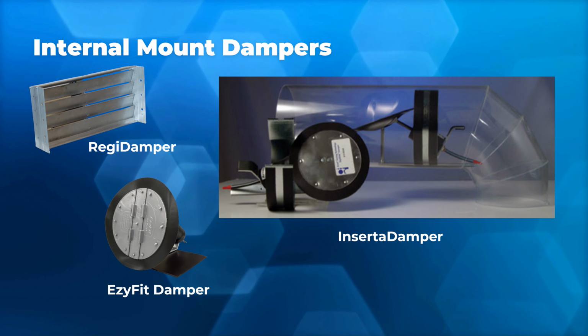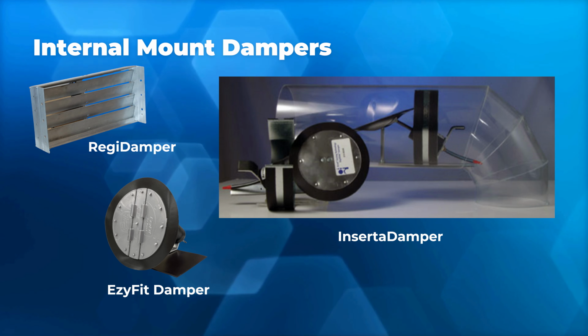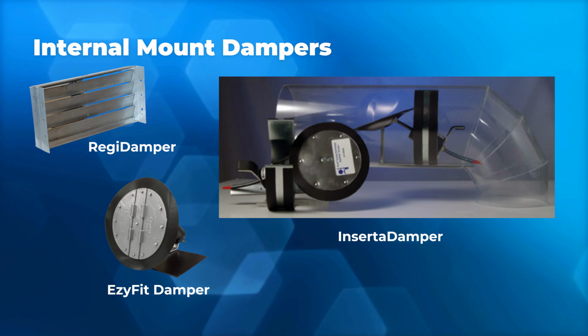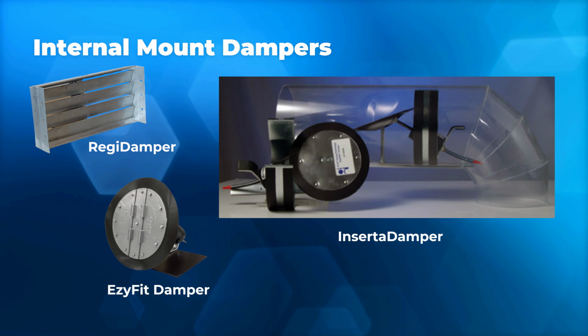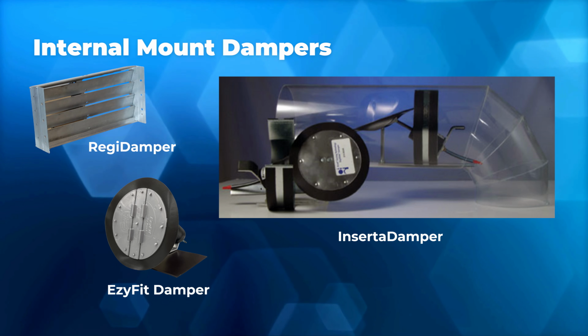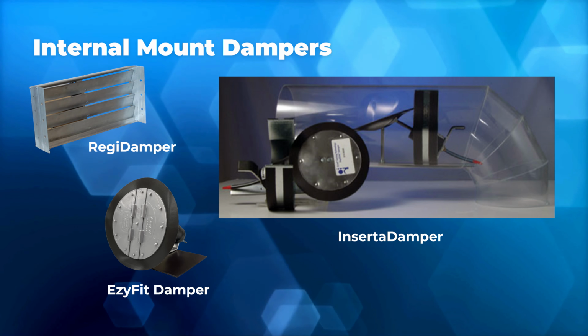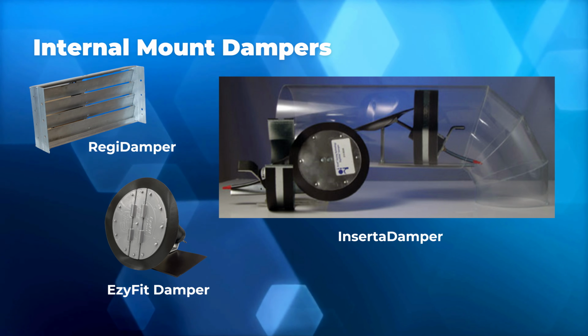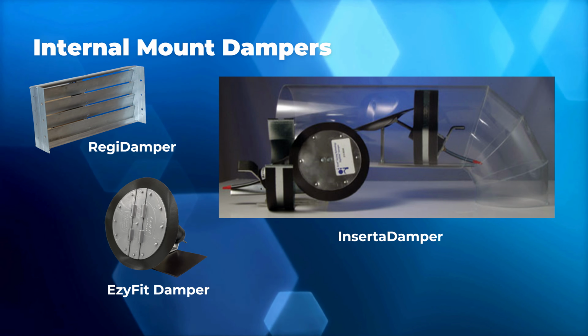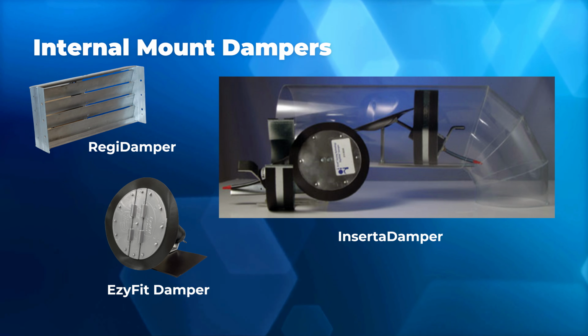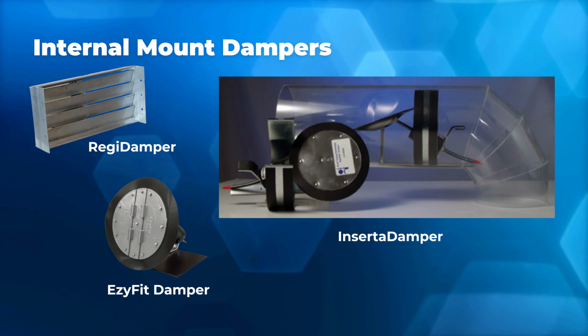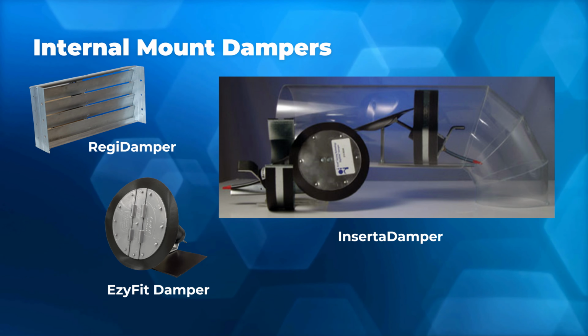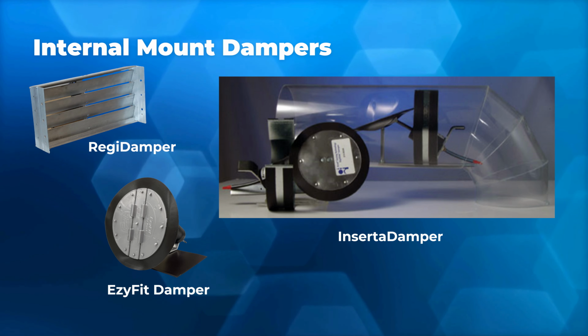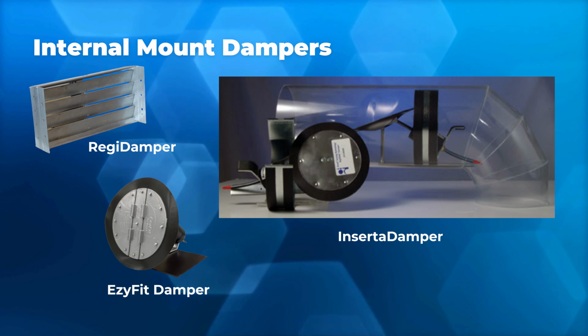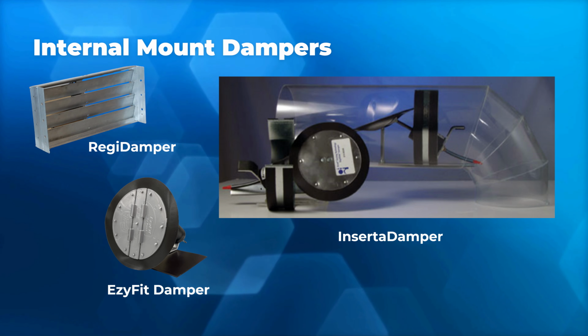And then you'd run your tubing through the ductwork itself to a centralized location in the basement, and then tie that into your panel itself. The only real drawback to the Regi damper is it's not a gasketed seal on the blades themselves. So you do get a little bit of air bleed by with this specific damper. It's the only damper that we do offer without that gasketed seal. But if you don't have metal ductwork and you got a slab home, something like that, it definitely will work for you. And it gives them an option of zoning where there is no real other option.